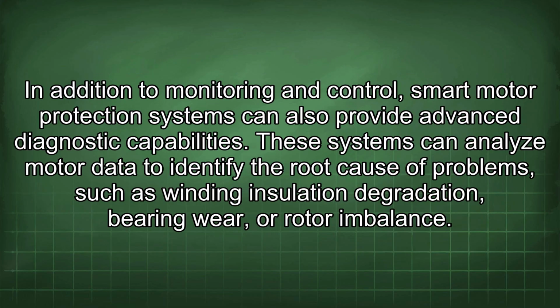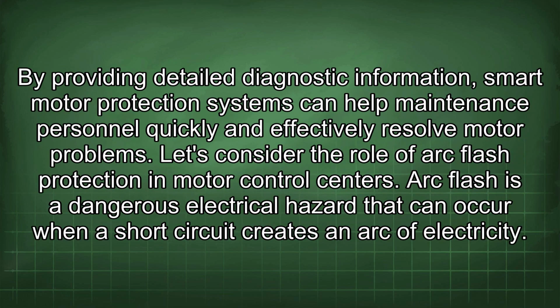In addition to monitoring and control, smart motor protection systems can also provide advanced diagnostic capabilities. These systems can analyze motor data to identify the root cause of problems such as winding insulation degradation, bearing wear, or rotor imbalance. By providing detailed diagnostic information, smart motor protection systems can help maintenance personnel quickly and effectively resolve motor problems.